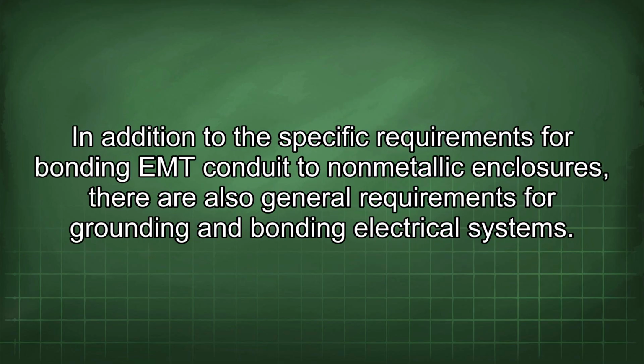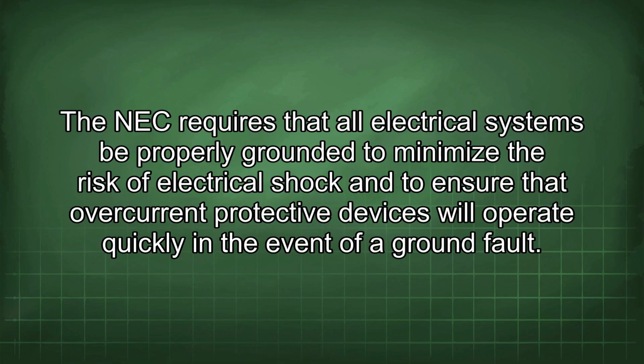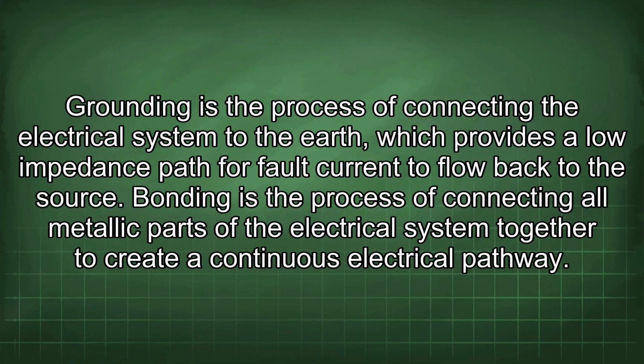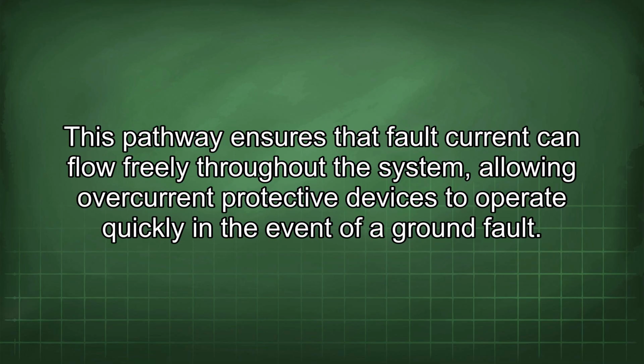In addition to the specific requirements for bonding EMT conduit to non-metallic enclosures, there are also general requirements for grounding and bonding electrical systems. The NEC requires that all electrical systems be properly grounded to minimize the risk of electrical shock and to ensure that overcurrent protective devices will operate quickly in the event of a ground fault. Grounding is the process of connecting the electrical system to the earth, which provides a low impedance path for fault current to flow back to the source. Bonding is the process of connecting all metallic parts of the electrical system together to create a continuous electrical pathway. This pathway ensures that fault current can flow freely throughout the system, allowing overcurrent protective devices to operate quickly in the event of a ground fault.